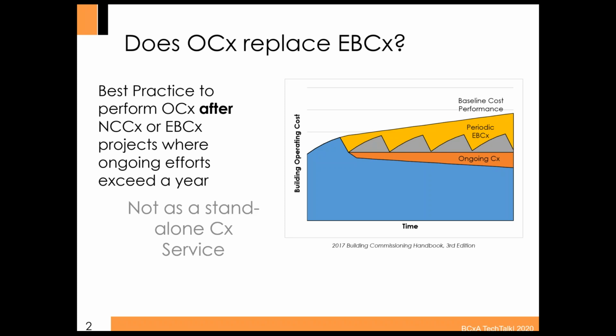Ongoing commissioning as a best practice is really meant to follow after new construction and existing building commissioning projects, where over a longer period of time we're looking to sustain the performance of the building. From a cost standpoint, we see the initial build of a building, new construction commissioning takes place, and we're optimized to design at that point. But naturally over time, the performance of a building and its systems will degrade.